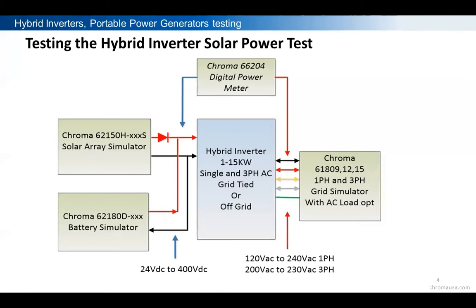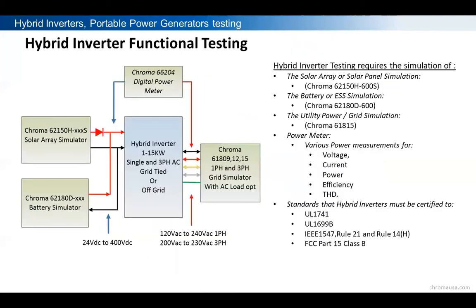They have various charging and discharging curves that we'll get into, and you have to simulate that properly to test and verify it with your hybrid inverter, which also acts as a battery charger and battery controller, taking that power and putting it back through to create AC. To simulate the grid, you need an AC source that's bidirectional, meaning it has to accept power from the inverter and put it back onto the grid, and also act as the grid when the inverter uses that power to charge the batteries. All of this combined is something Chroma has put together with our R&D group, including a digital power meter to tie it all together for even better and more accurate measurements.